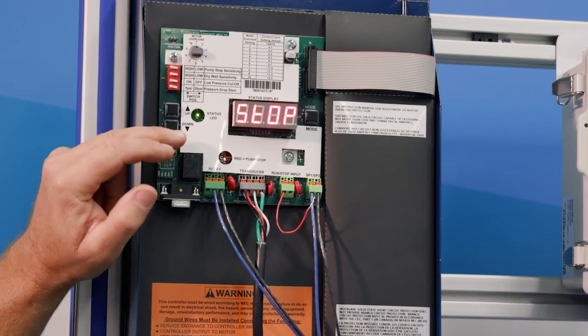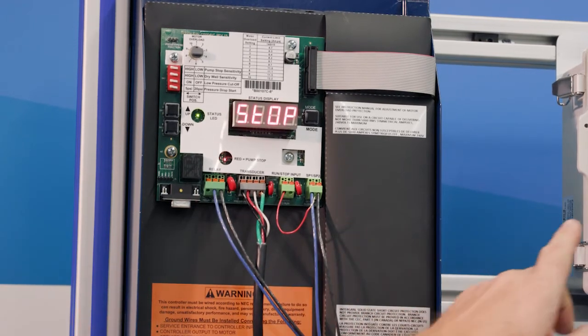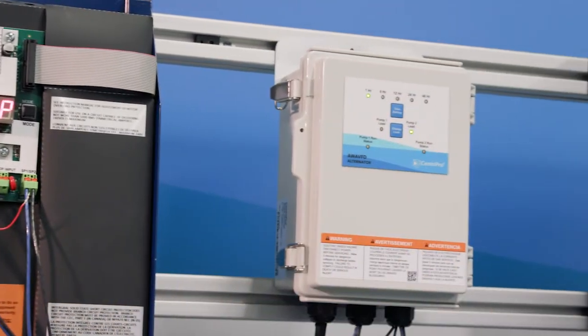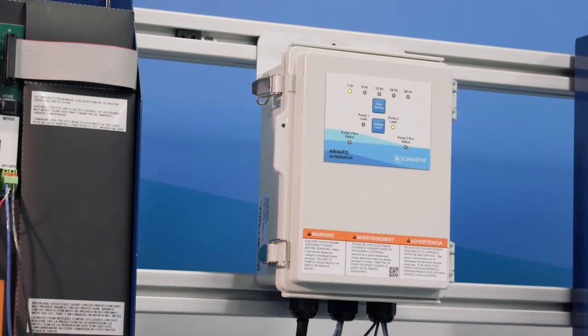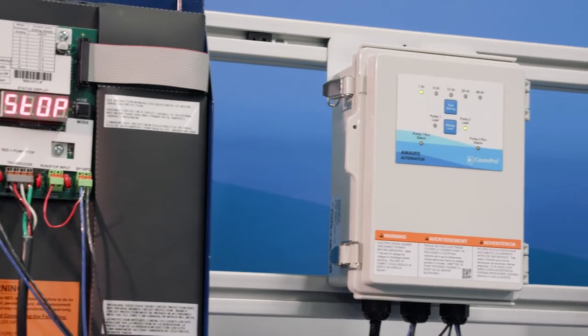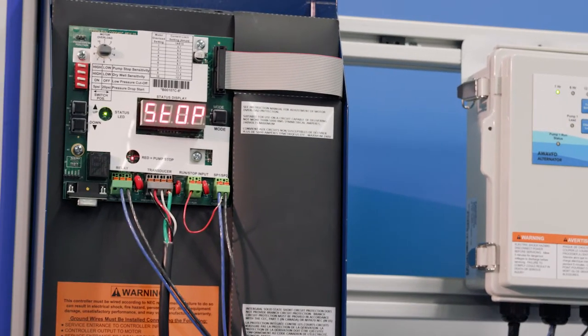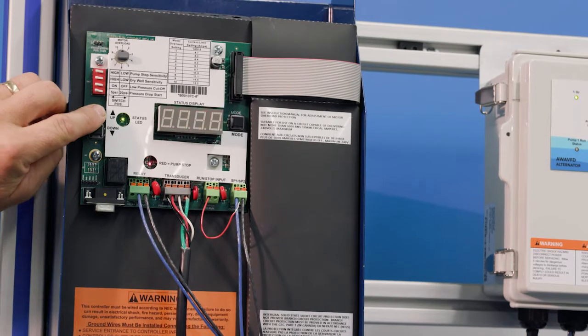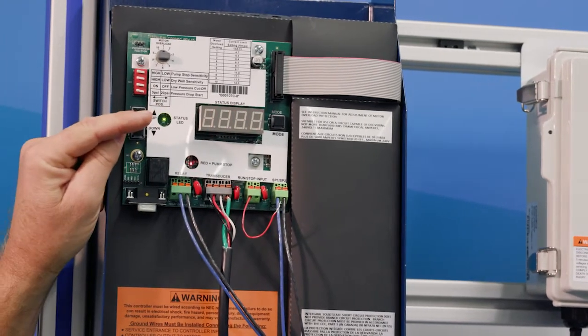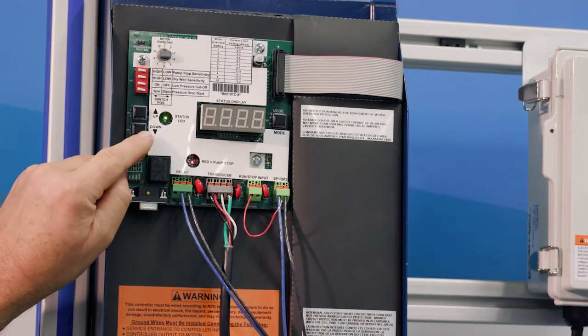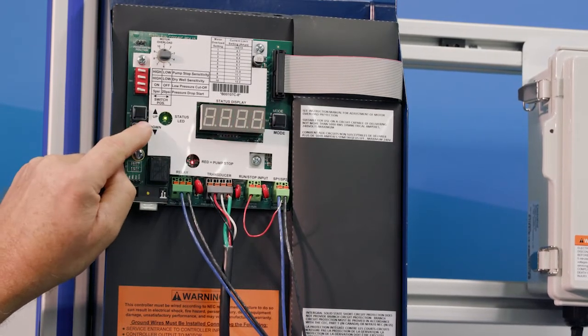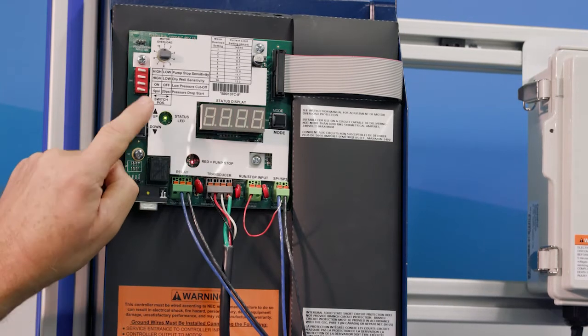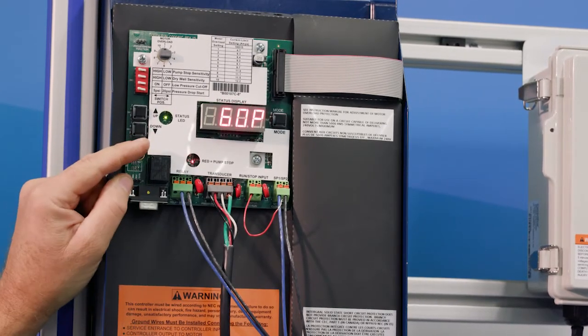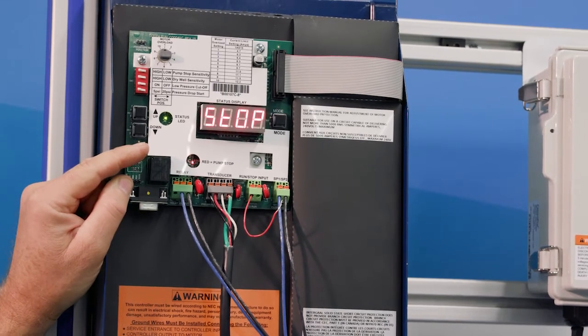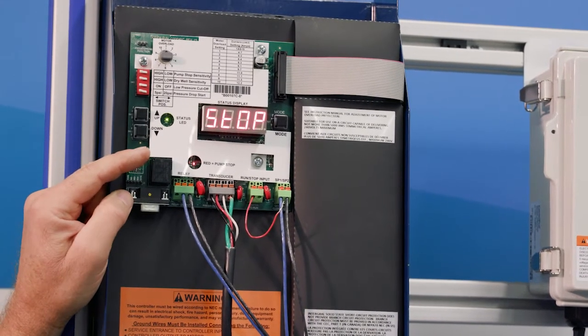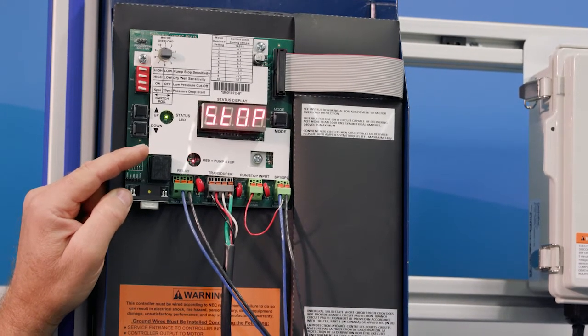So how do I set the lag? Well, what I have to do is change the lead to number 2, which means number 1 is the lag, right? And I can confirm that by simply pressing that up button again. SP1, remember, that is our lag pressure here. SP1 is 60, and we could change that. So let's go with 60 on SP1. Again, our lag pressure, our lower pressure. So we have a difference of 15 psi between the lead and the lag.